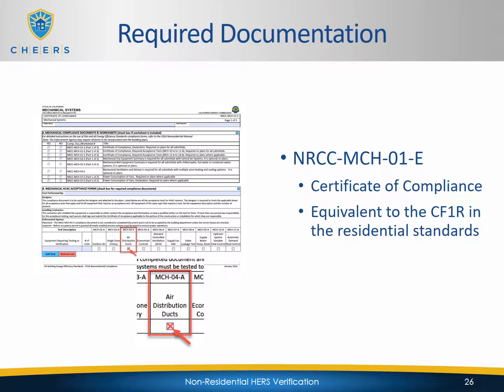Now let's look at the required documentation needed before performing your duct leakage test. The first document is the Certificate of Compliance, the NRCC-MCH-01-E — equivalent to the CF-1R in residential standards. This is the design document. In Section B, the test description highlighted in the red box, if that box is checked, it indicates that a duct leakage test is required for that particular system via the MCH-04-A.